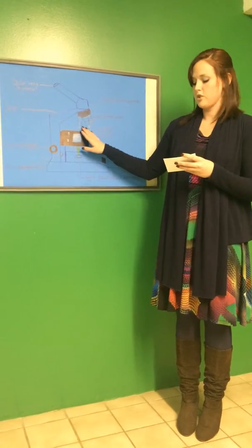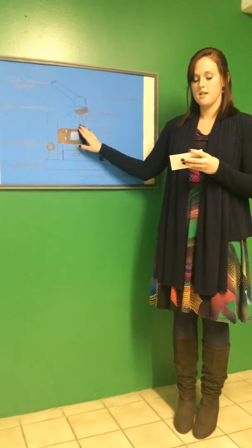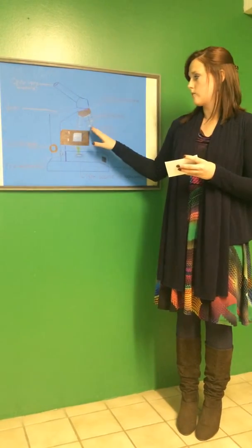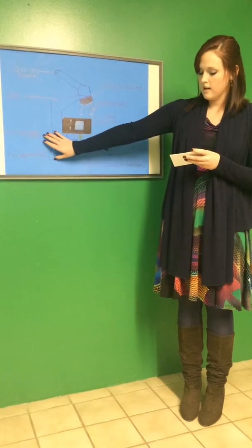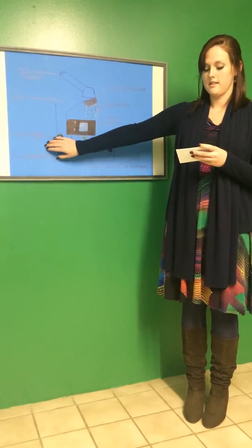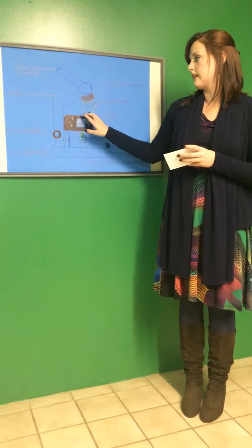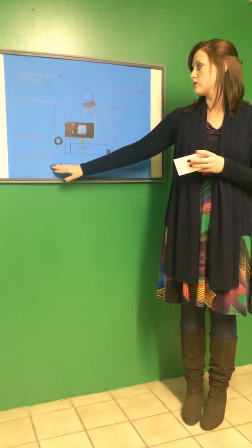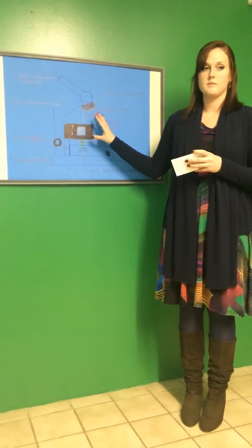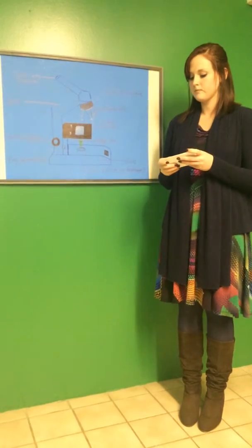The 4x objective lens is the smallest. You'll always start with that. You'll go up to the 10x, 40x, and 100x objective lens. The focusing knobs are used to focus the specimen clearly. The coarse adjustment knob is used on the 4x objective lens and the 10x, and the fine adjustment knob is used to focus on viewing specimen in the 40 times and the 100 times magnification.